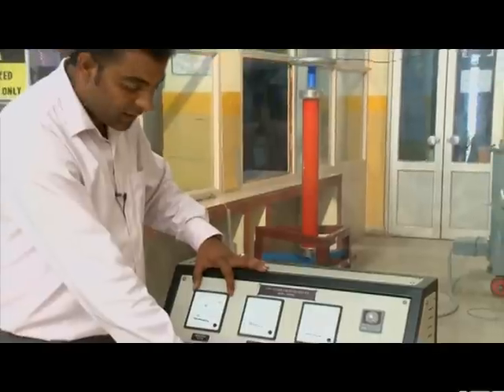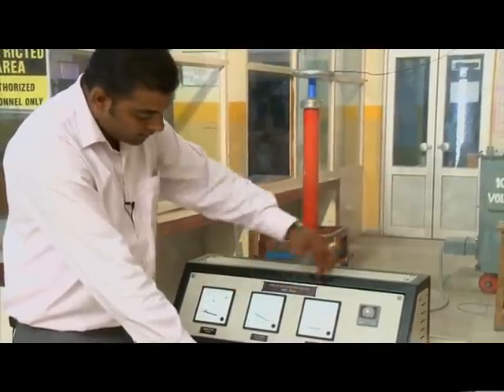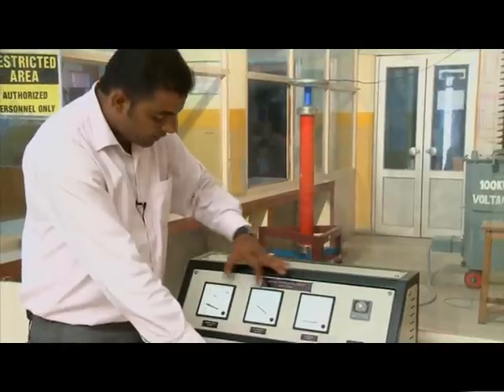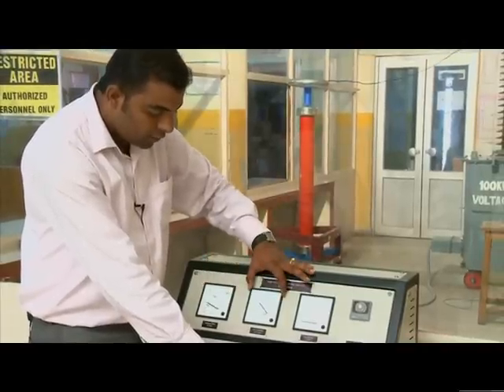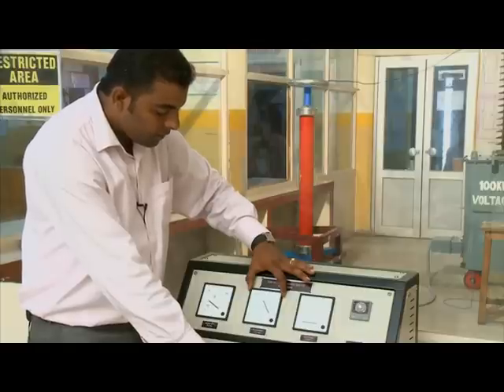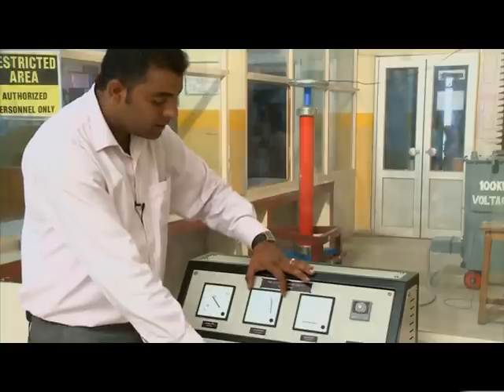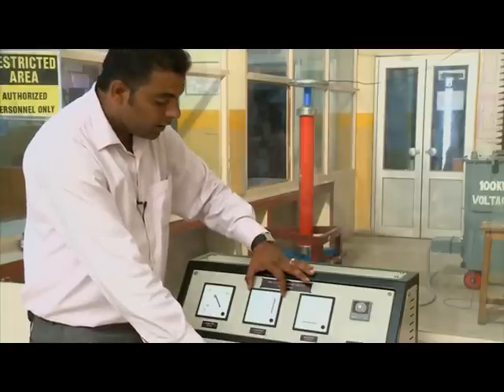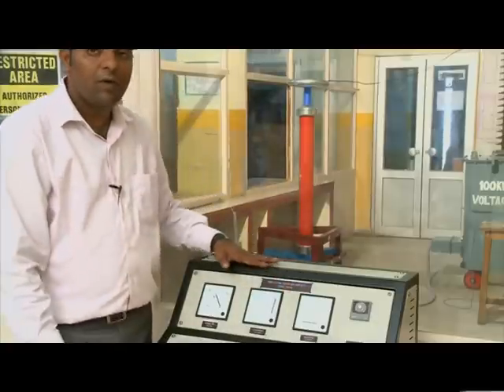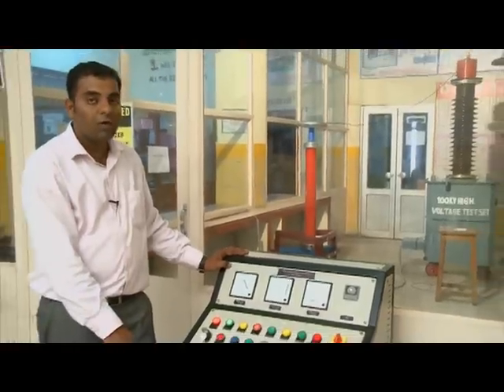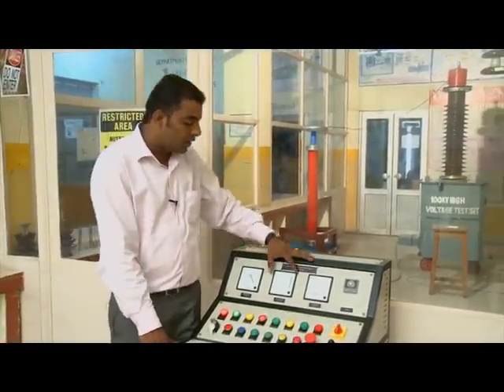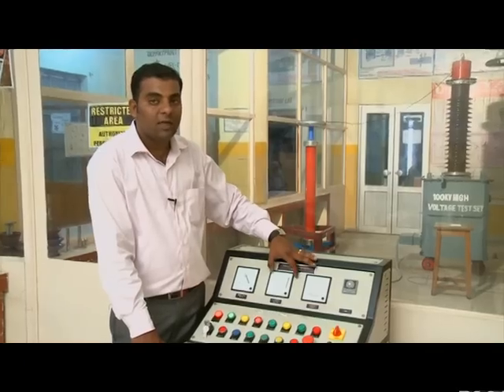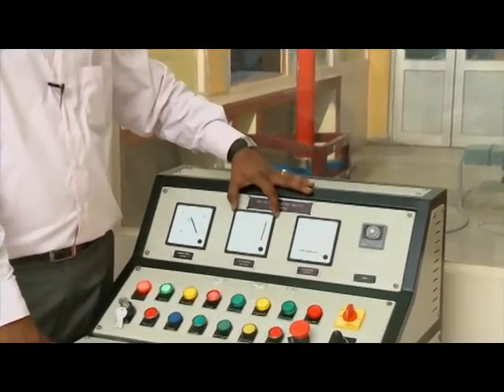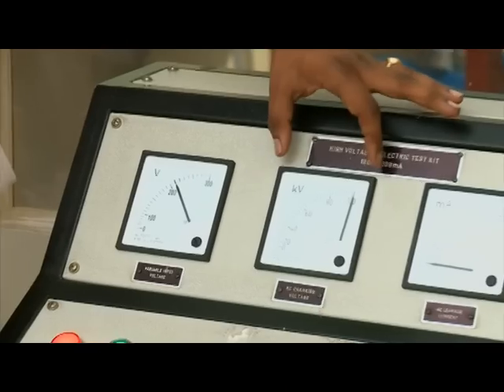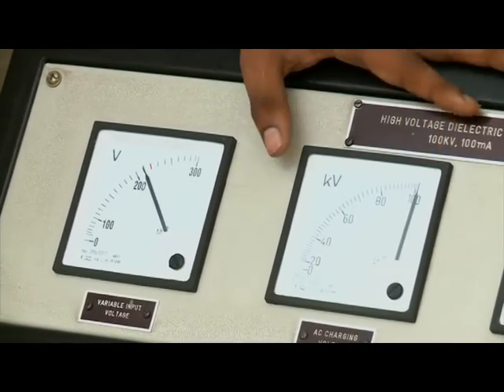When we increase the HT, the input voltage will also increase, and with this increment of input voltage, the output voltage will also increase. On a particular value of output voltage, a hissing sound will occur, and when the hissing sound occurs, it will be the maximum value of transmitted voltage. On that value, corona loss will be generated in the transmission line. To reduce this corona loss, the transmission of the voltage will be kept below that critical value.